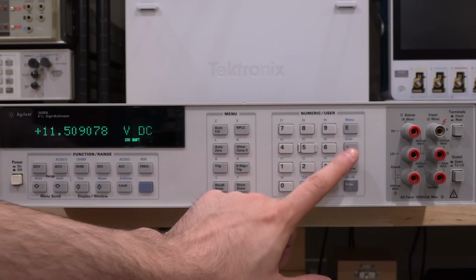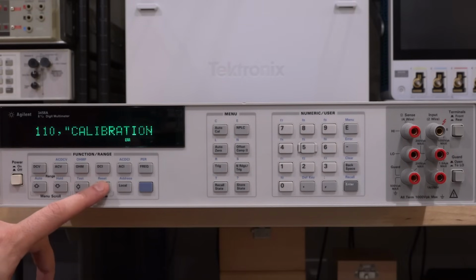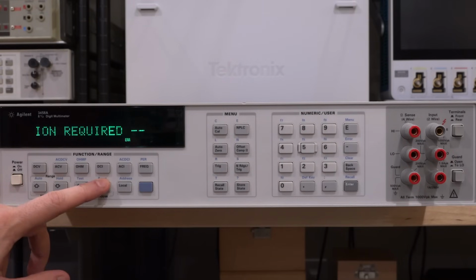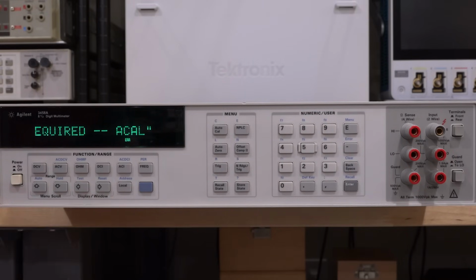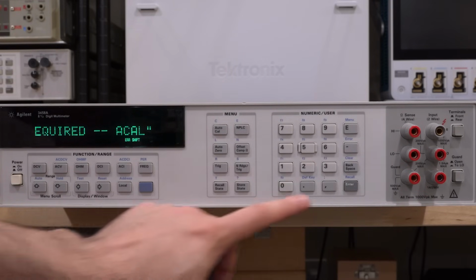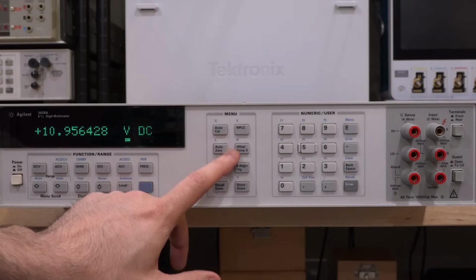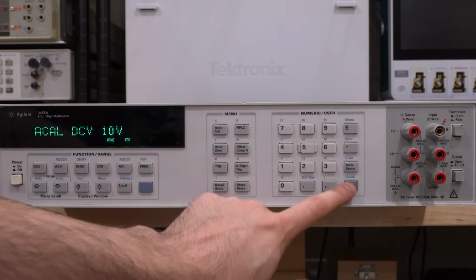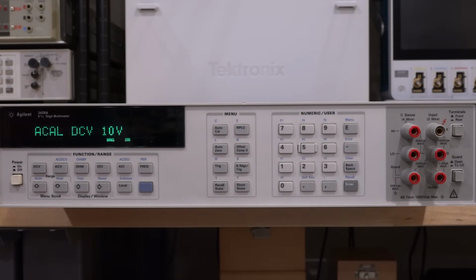So if I go over and look at the error, you can see that it's asking that we should perform an ACAL. And that's most likely because either ACAL hasn't been run or something's happened or the last time it's failed. So therefore, we should be able to go back and perform an ACAL and see what happens. There we go. Now let it run. This is going to take a little bit of time.